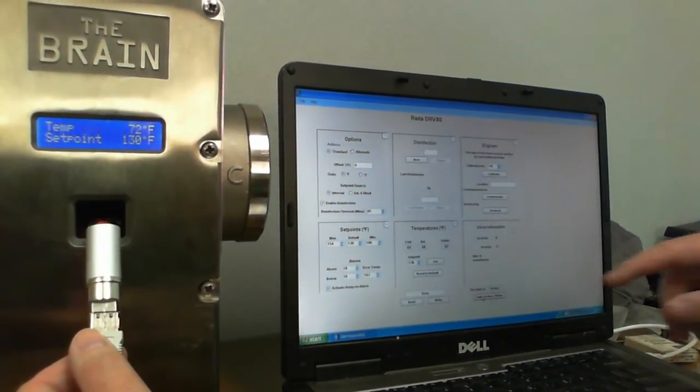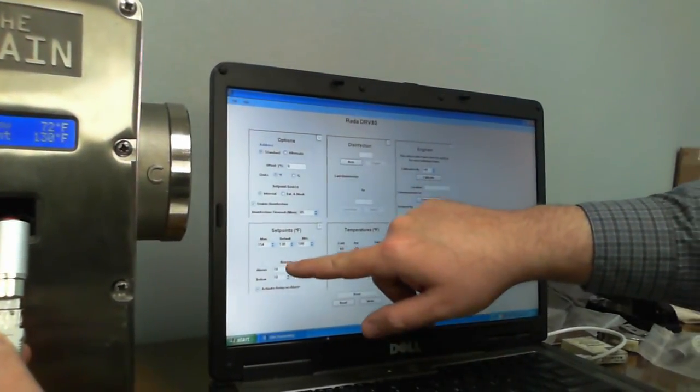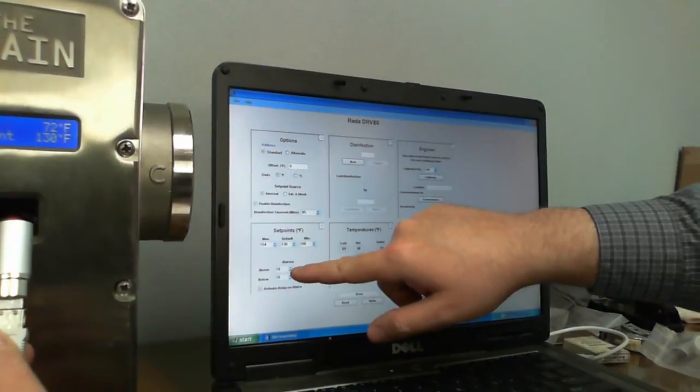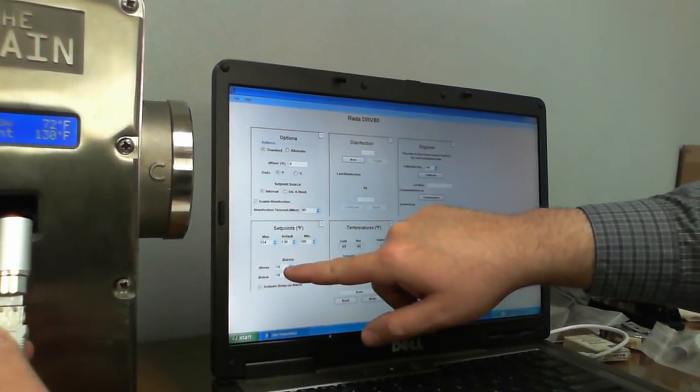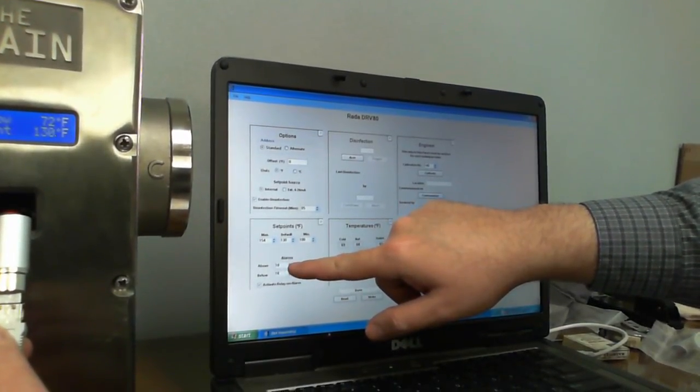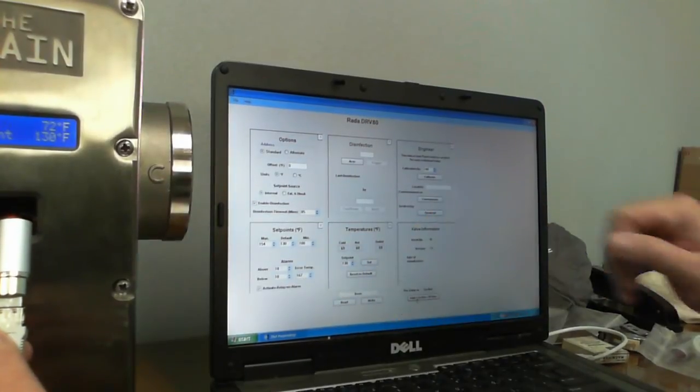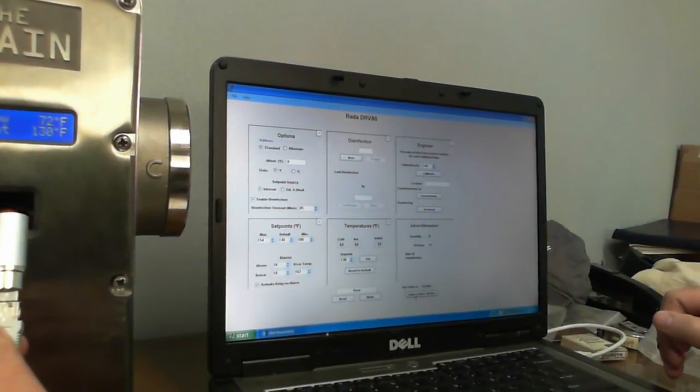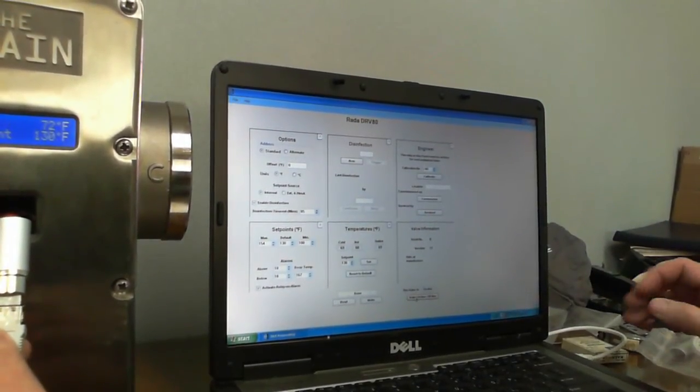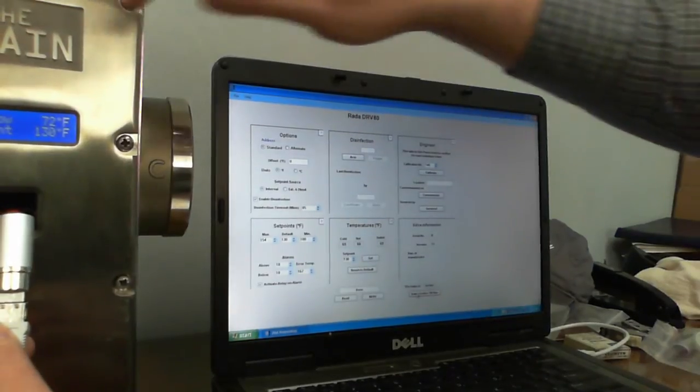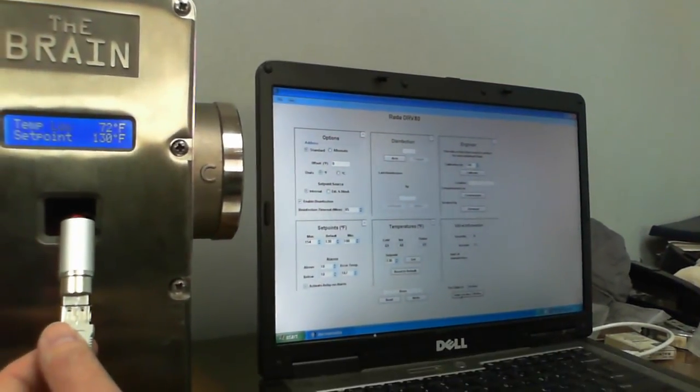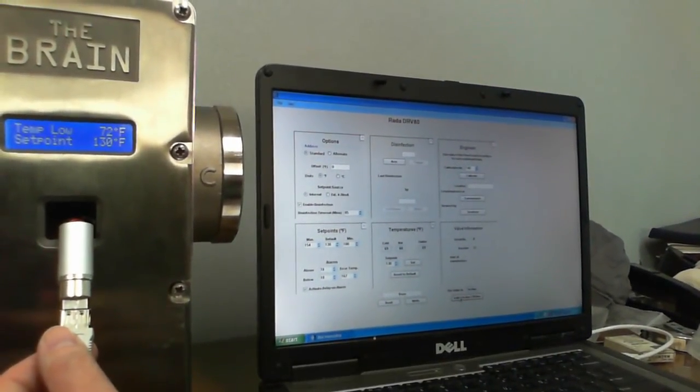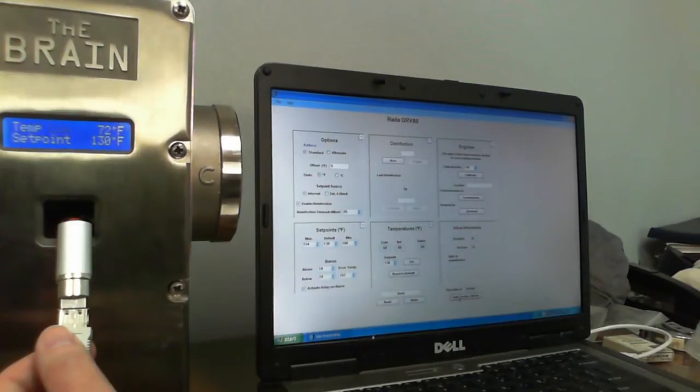Common other changes you might make is you might change your alarm settings here, which basically these numbers are the number of degrees above or below your set point. And that would just give you a flash an alarm. If it's a low temperature, it'll flash temp low. If it's a high temperature, it'll flash temp high.